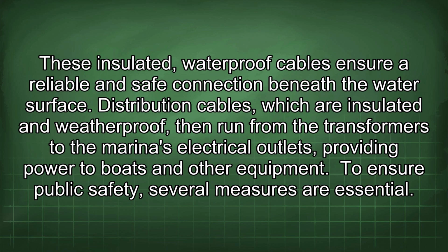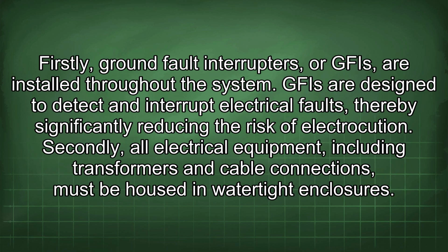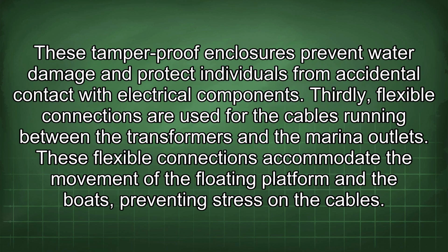Distribution cables, which are insulated and weatherproof, then run from the transformers to the marinas' electrical outlets, providing power to boats and other equipment. To ensure public safety, several measures are essential. Firstly, ground fault interrupters, or GFIs, are installed throughout the system. GFIs are designed to detect and interrupt electrical faults, thereby significantly reducing the risk of electrocution. Secondly, all electrical equipment, including transformers and cable connections, must be housed in watertight enclosures. These tamper-proof enclosures prevent water damage and protect individuals from accidental contact with electrical components.